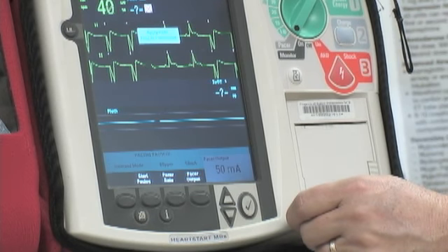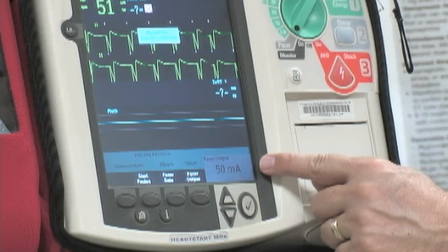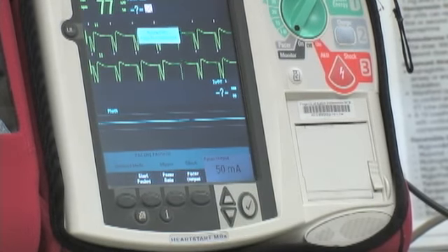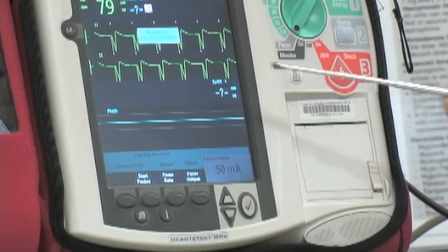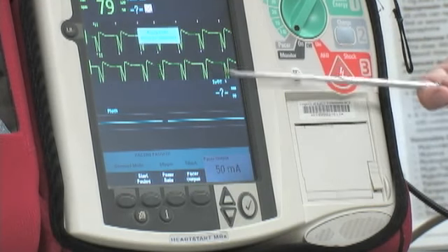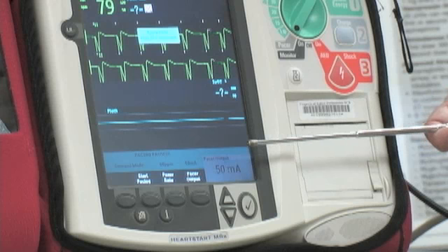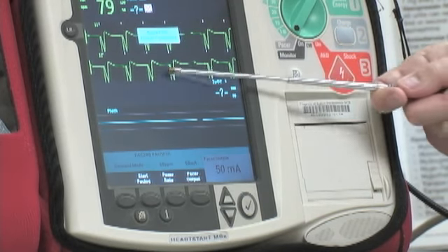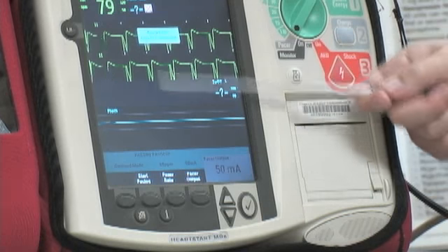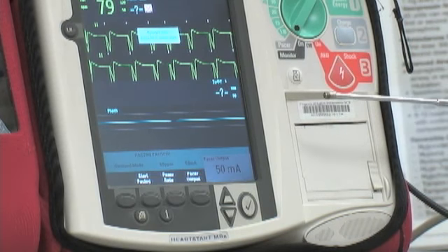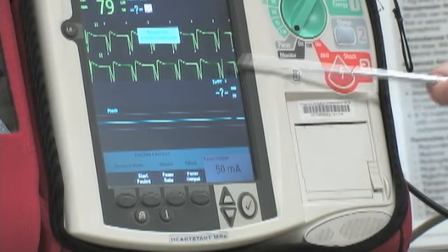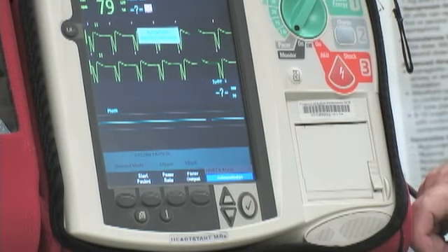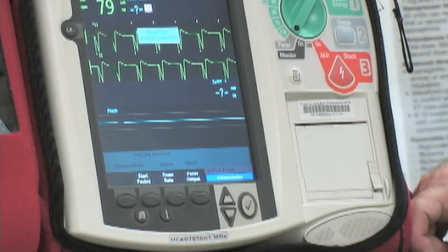There we go. Aha. Okay, so at 50 milliamps, we see a pacer spike followed by a wide QRS each and every time. So this illustrates that we've reached electrical capture with our transcutaneous pacer, and it's consistently capturing each and every time. Spike followed by a wide QRS.